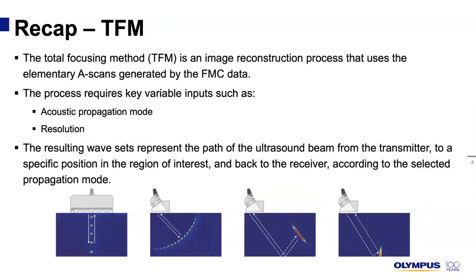TFM, or Total Focusing Method, on the other hand, is an image reconstruction process that uses those elementary A-scans. The process requires key variable inputs such as acoustic propagation mode and resolution. Acoustic propagation mode means whether we are going to use longitudinal waves, transverse waves, whether we're going to skip, mode convert, etc. Resolution refers to how fine or coarse our grid of inspection is going to be.